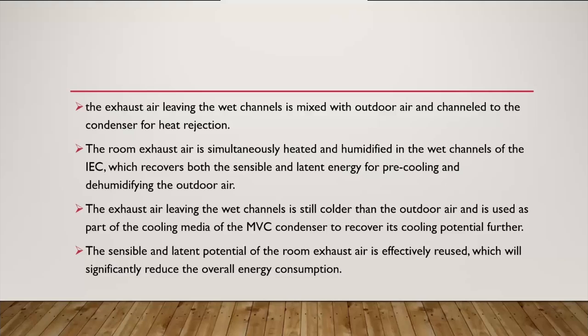The exhaust air leaving the wet channel is still colder than the outdoor air and is used as part of the cooling media of the mechanical vapor compression condenser to recover its cooling potential further. The sensible and latent potential of the room exhaust air is effectively reused, which will significantly reduce the overall energy consumption. That's all for the methodology.